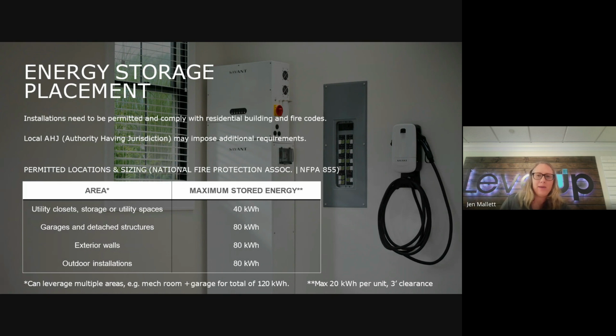This is from the NFPA, the National Fire Protection Association, who has done work on permitted location and sizing for energy storage, which is really home batteries. In utility closets, storage, or utility spaces, the NFPA says your maximum stored energy is 40 kilowatt hours. For garages and detached structures, which are probably the most frequent use of home batteries, you're looking at double that, 80 kilowatt hours. Exterior walls and outdoor installations also allow 80 kilowatt hours.